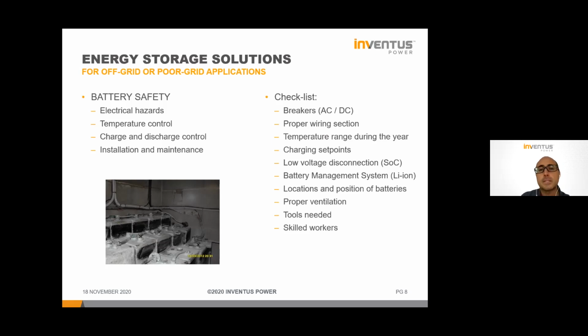Charging set points, as Pablo mentioned before, are super important to really charge the batteries with the correct algorithms and charging settings, otherwise we run into bad performance. Also the low voltage disconnection: you need to set this up so as not to fully discharge the battery.